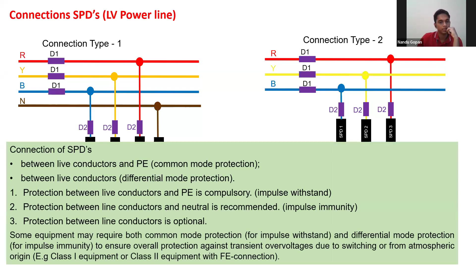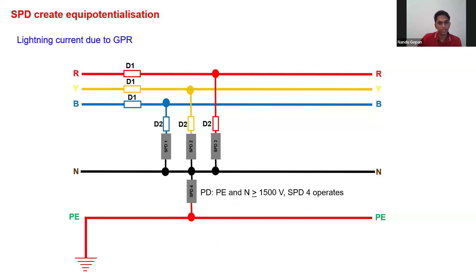So there is a lightning strike, and there is a potential increase, GPR, in the PE conductor. You see, this potential difference will be very high voltage, because this is a lightning current. If you don't have an SPD, the insulation between all these conductors can go into a flashover. So what happens is, SPD4 will first start working. It will make the voltage between neutral and PE the same. So the SPD works, and the voltage between neutral and PE becomes the same for that microsecond.